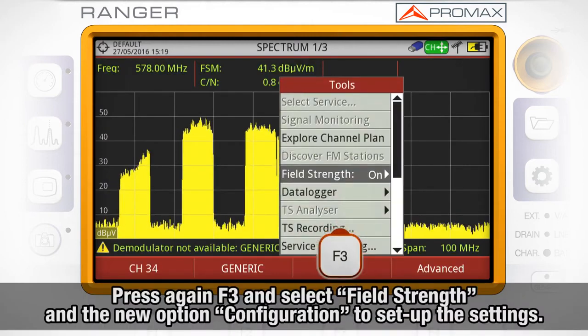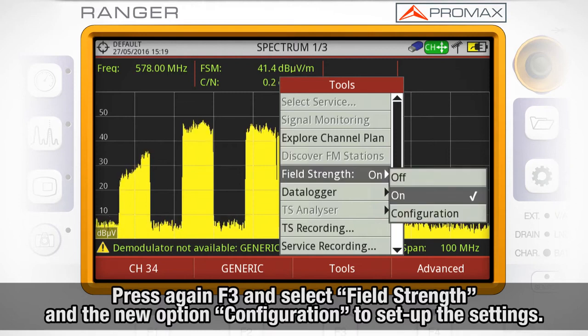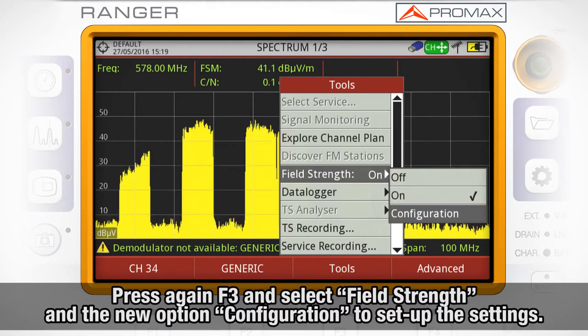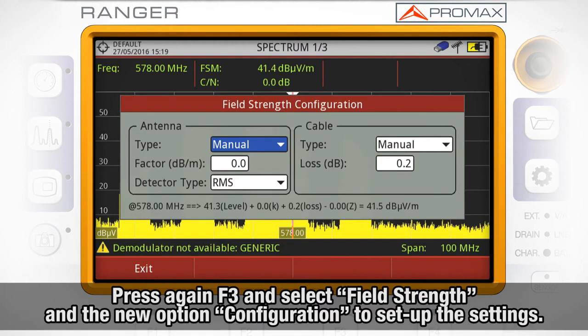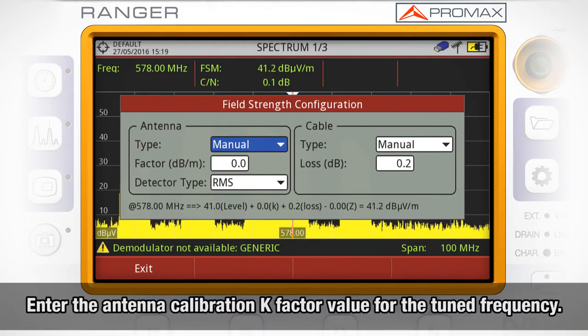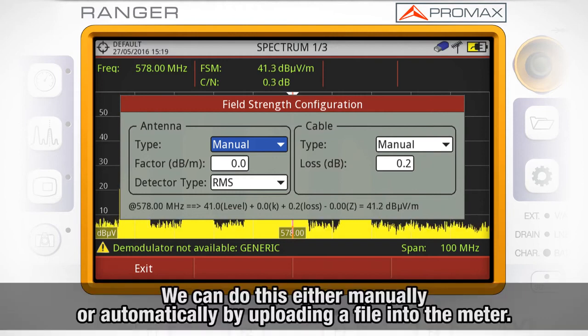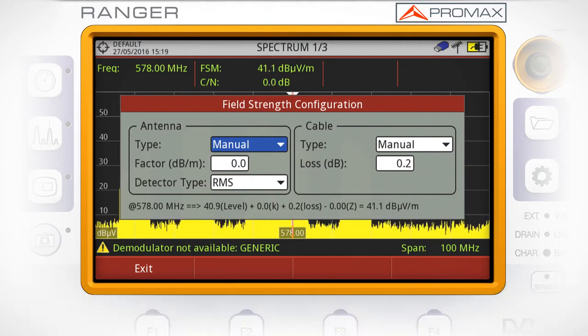If we press again F3 and select Field Strength, we will see a new option, Configuration, which will lead us to the settings menu for this tool. We will need to inform the antenna calibration K-factor value for the frequency we are tuning. We can do this either manually or automatically by uploading a file into the meter with that information.